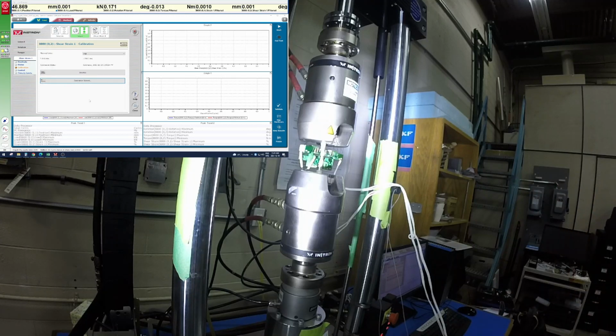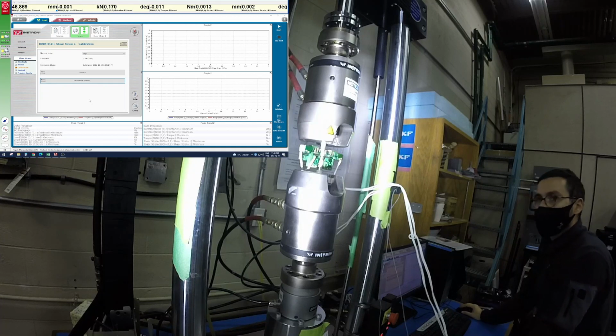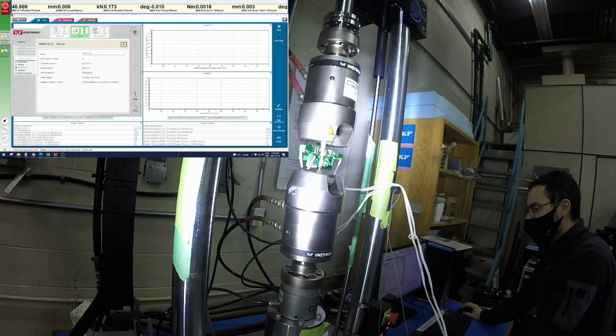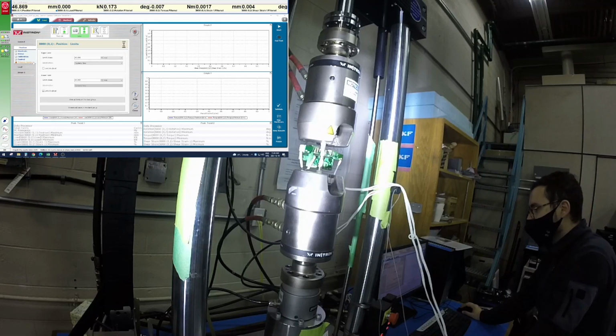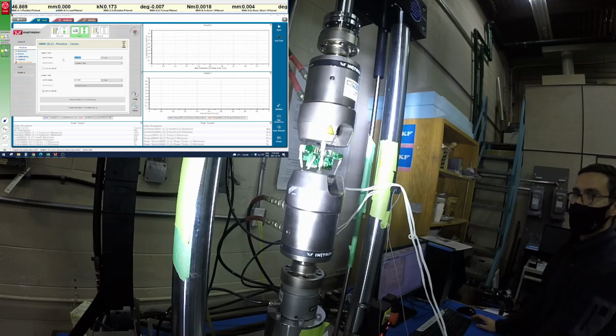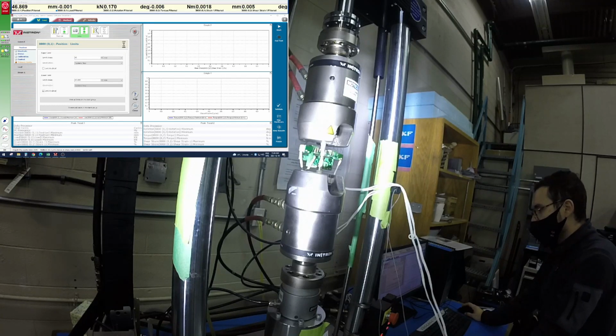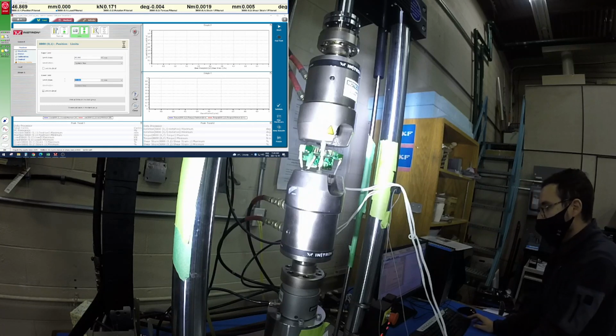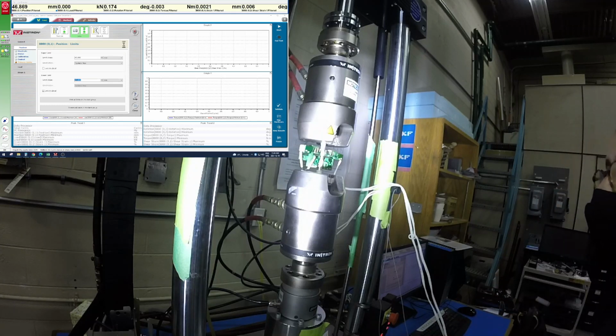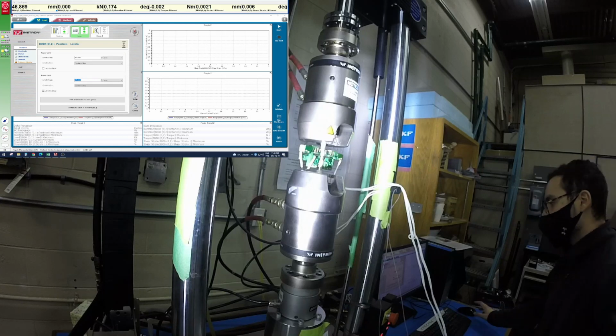What we now want to do is ensure that before we do anything to actually use the machine and move the actuator around, we want to make sure that the extensometer is protected and it's not going to get damaged. So we can see our position, which is probably the most important thing, on the top left here. We want to go back to the axial channel and go to position. We want to make sure that our primary limits, which are safety limits effectively, we're going to set to 48, which allows some movement, as an upper limit, and maybe 44 for a lower limit. This is really dependent on the strain of your test. And you want to make sure you click enter there. That is a very common mistake. Make sure you click enter to save those parameters for your limits.